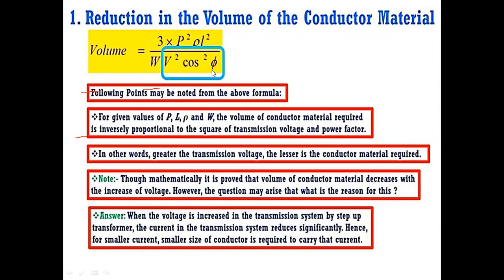Okay, so now consider the rest of the variables as constant, because we are only dealing with the volume and the voltage. So the volume of the conductor is inversely proportional to the square of the voltage. It means if the voltage is increased, the volume will be decreased by the square times. So if we have high voltage, the conductor size will be reduced.